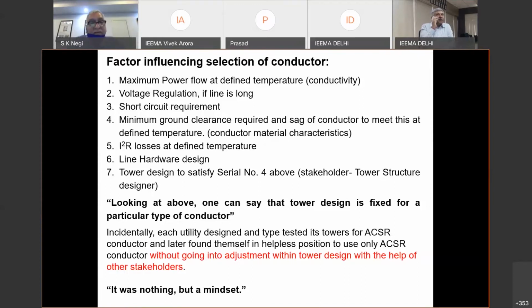Line hardware design is definitely another factor, because as you select an HTLS type of conductor, definitely the hardware design and material has to be taken care of to withstand that kind of temperature. And then tower design to satisfy serial number 4, the ground clearance and all that. As I already said, we were stuck with the particular type tested design in a utility, and thereafter not much thought was given, not much help was taken from the designer, on how best we can use the other conductor in the same tower. Those are the important factors to be considered.